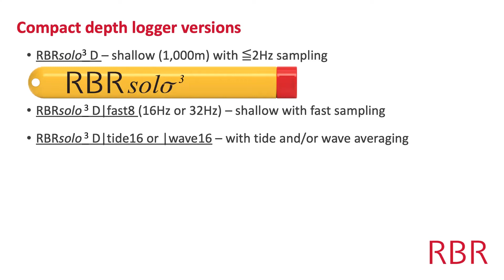And we also provide it with tidal averaging firmware, and wave analysis and statistical firmware as well, inside the logger. The deeper version looks very similar, but it's made out of titanium, with the same type of pressure sensor in the end. And then we also produce a version that adds a temperature thermistor, if people are interested in temperature as well as pressure. The Duet TD, which again is available in the same firmwares, and also in titanium.